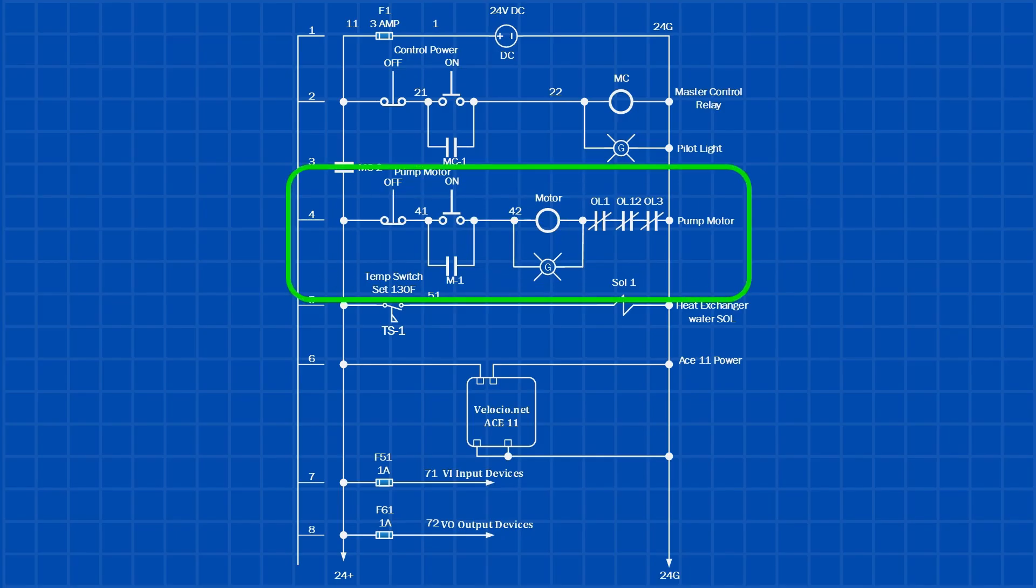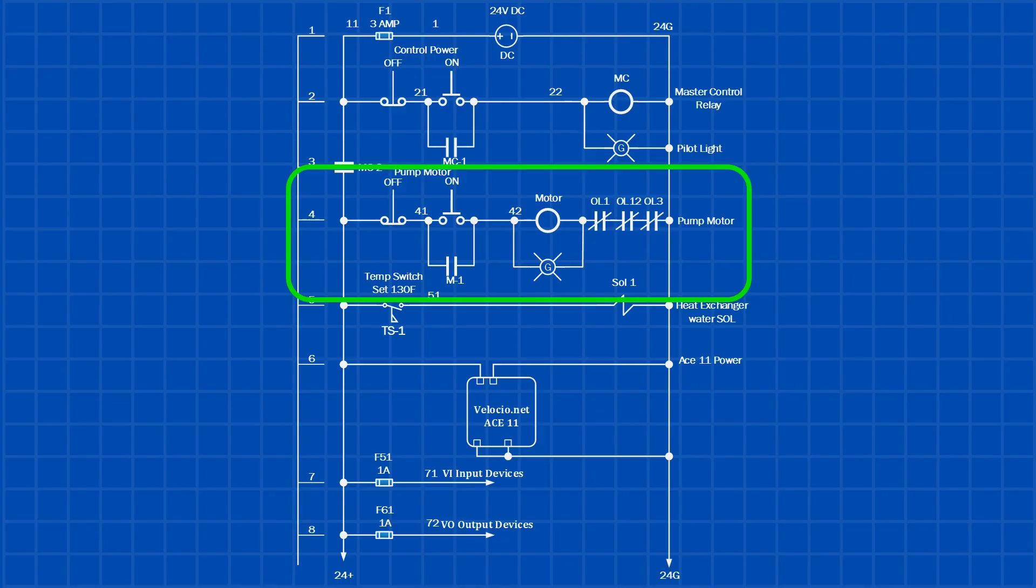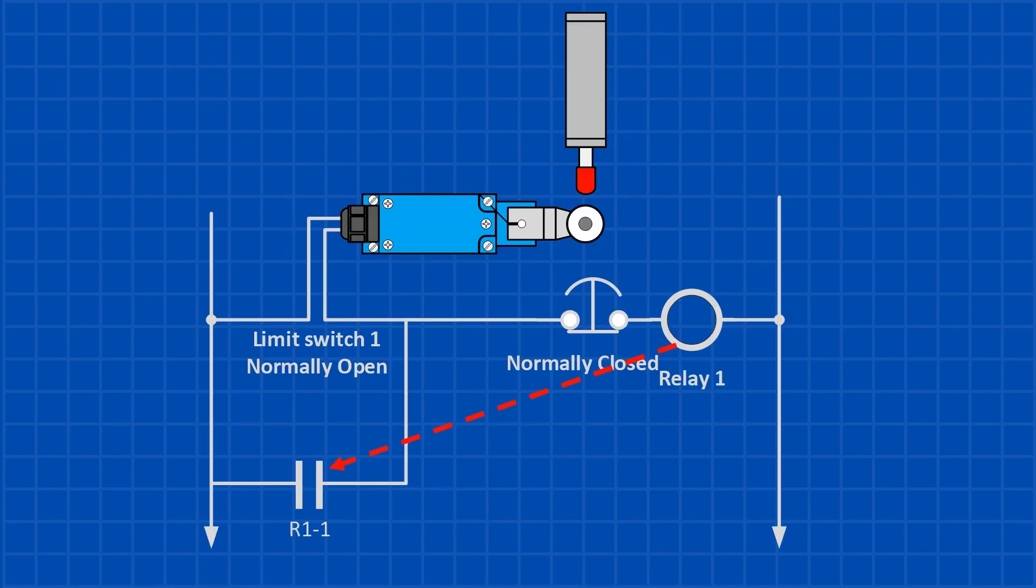Another common use of a latching relay is in motor control circuits. Here, we use a latching circuit to start and stop the motor. The auxiliary contact M1 from the motor starter is wired in parallel with the start button. This keeps the motor running after the button is released. Pressing the stop button breaks the latch, and the motor shuts down. To start it again, you have to press the start button once more.